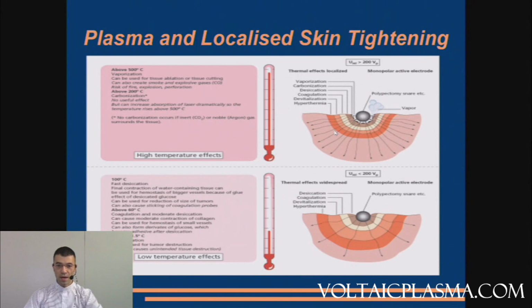This is just to show you that it's not only the empiric results that show a certain amount of heat released into the skin, causing a certain amount of burn. This is also common knowledge in the literature and in science, that when you apply electrofulguration onto the skin, you get a certain amount of heat released into the skin, and you cannot avoid that by design.